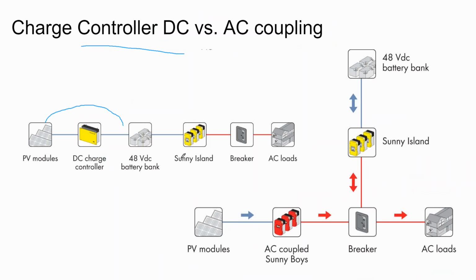It also comes down to a siting issue. If all your electronics are in the same location, that's a good opportunity for DC coupling. But if you're building a microgrid where your solar array interconnects at a completely different point on the facility than where your battery inverter is located, for reasons like temperature, raw space, or noise, that's a reason to go with an AC coupled system even if you're starting completely from scratch. And in that AC coupling system, you can always use a generator as well, as we've discussed.